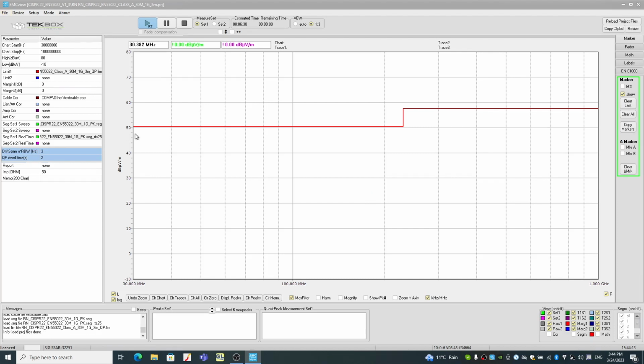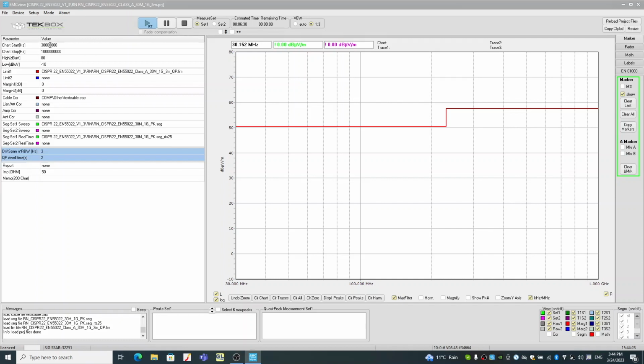Okay, so we load the project file, and as you can see the test limit is loaded - that's the 3 meter far field test limit line. That's fine, frequency range between 30 megahertz all the way up to 1 gig, and we wanted to really test that frequency range. So that's also good, and the next thing is to do the scan.